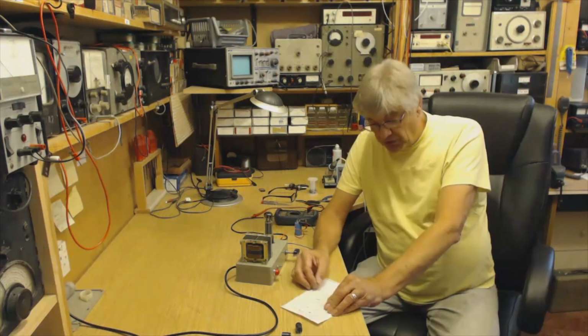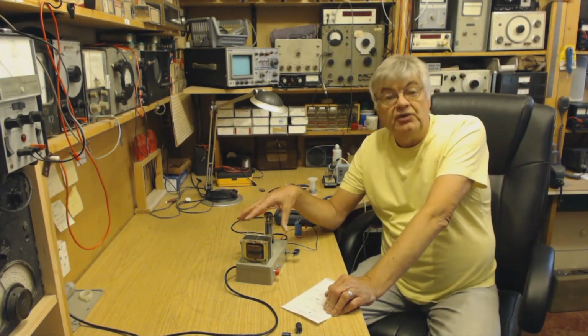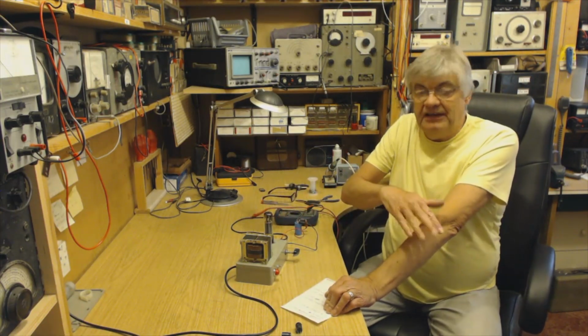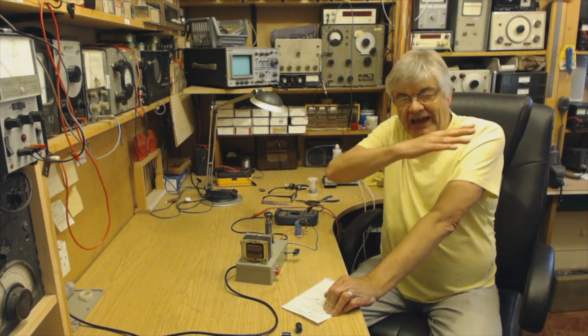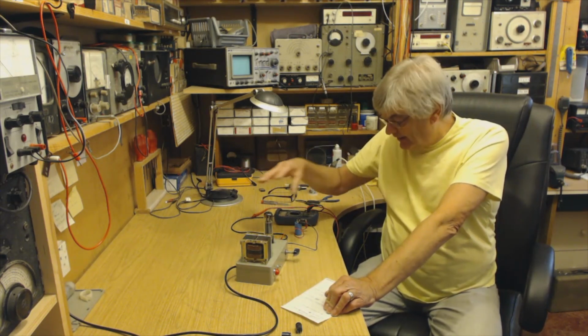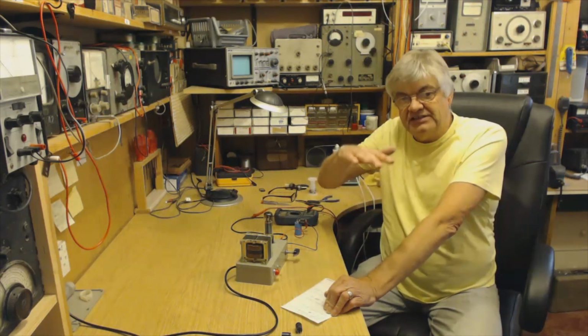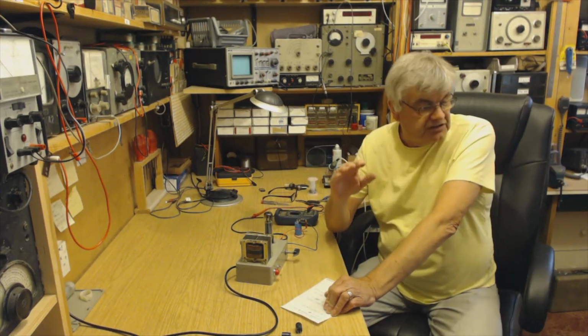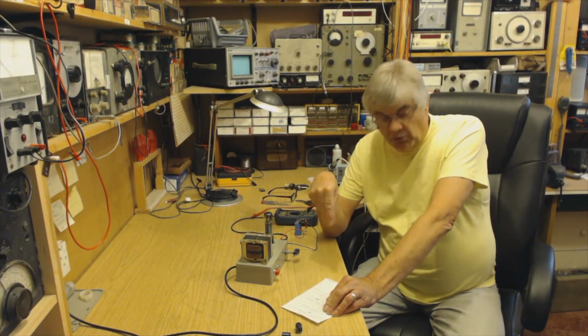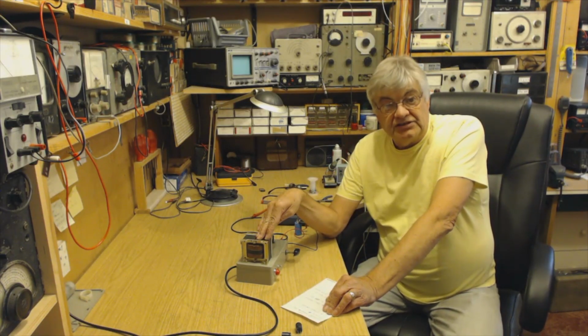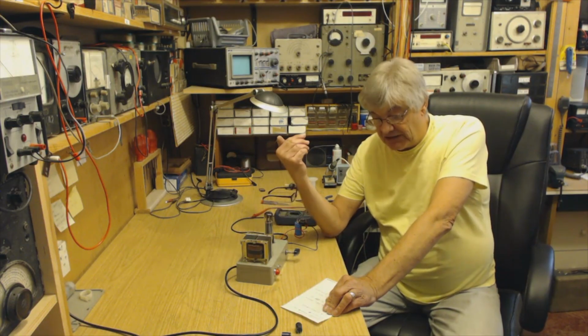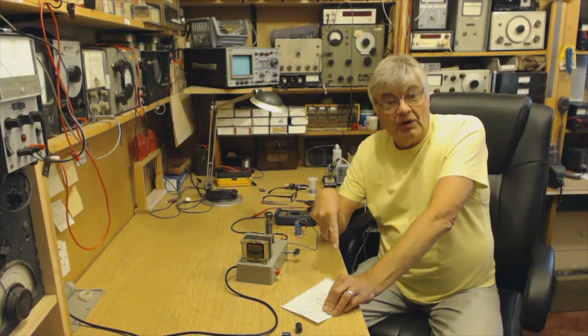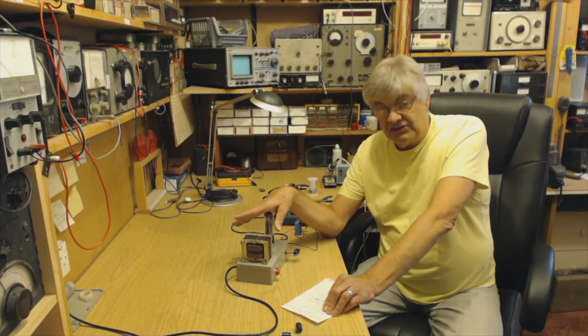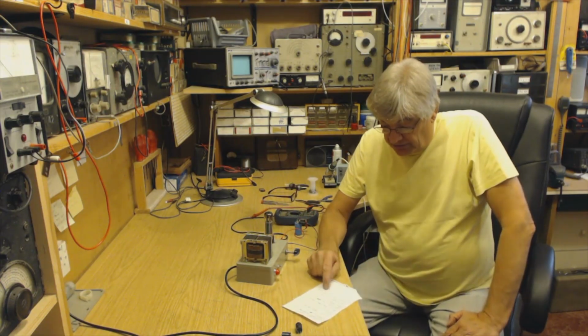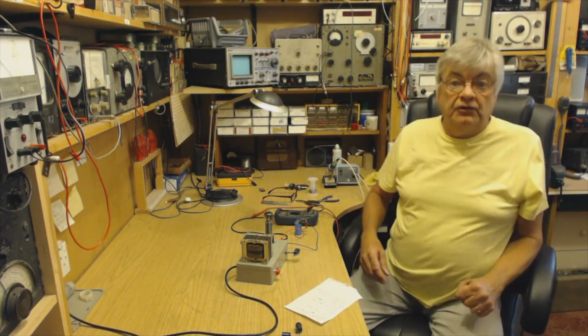That's the RMS. If you add smoothing capacitors, it increases the average DC voltage. The way to work it out: 460 volts AC coming out of the transformer, multiply that by 1.4 if you've added smoothing capacitors, and your DC will be 644 volts.